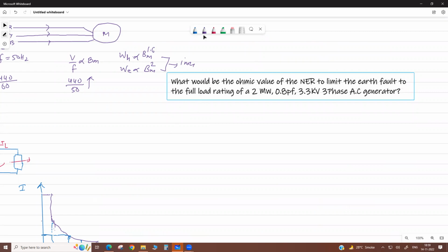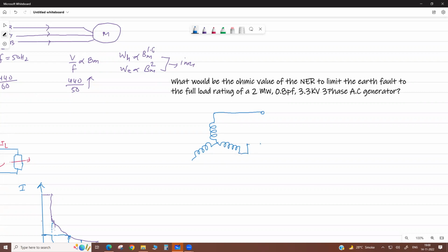He says, suppose there is an alternator; this alternator is always star connected. How do we do the grounding here? This neutral point is grounded through some resistance. We put a resistance here. Why is this resistance required? To limit the earth fault current.